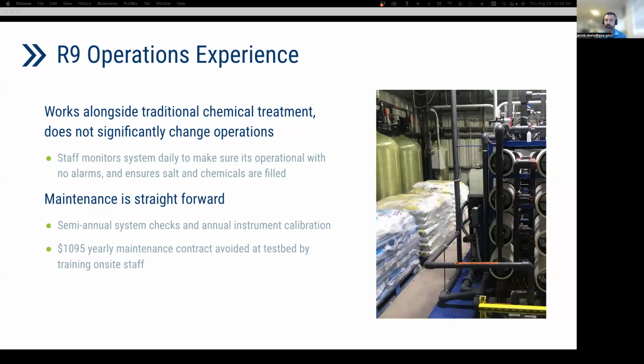We have several systems that require salt, so we just keep a pallet of salt inside the room, and a couple times a month the mechanics have to check the salt levels and add salt. The blowdown recovery system does have an anti-scalant and a cleaning solution, so we had to monitor that. Since it's been in system, we've had to replace the anti-scalant barrel one time, and there are filters on the system that need to be replaced every few years.